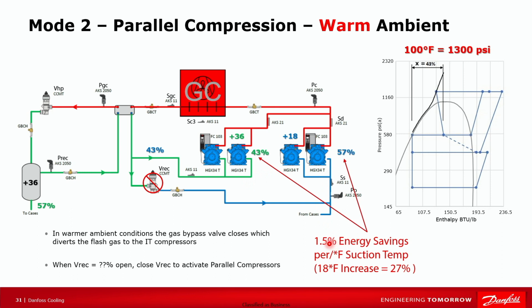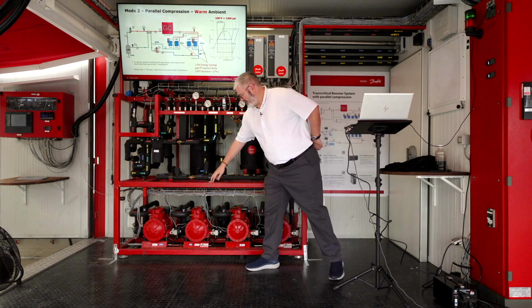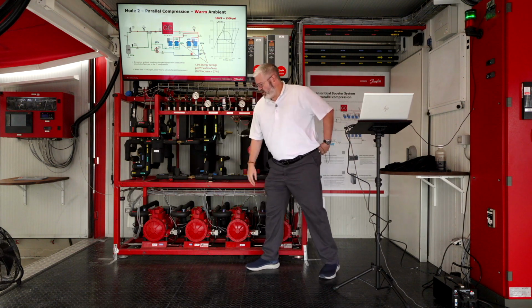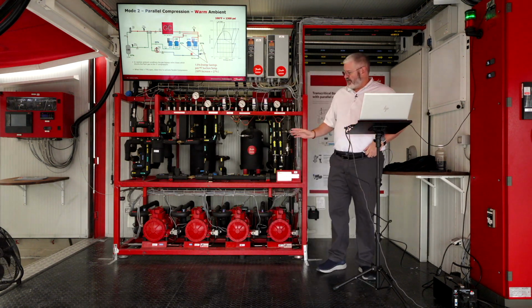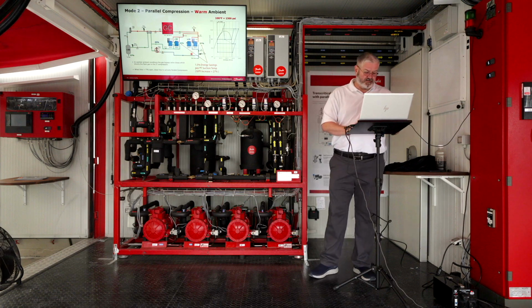And it literally lets you save about 30%, depending on the difference between the parallel compressor set point and your medium temp suction set point. And just food for thought, the set point for the parallel compressors will be flash tank pressure. We typically will float that up. When we close the receiver valve, we'll float the flash tank pressure up about 4 degrees to maximize that savings. So that's what parallel compression does. And on this system, on this unit, it's these two here. When we're operating in parallel compression, we're diverting part of our load over to those compressors.